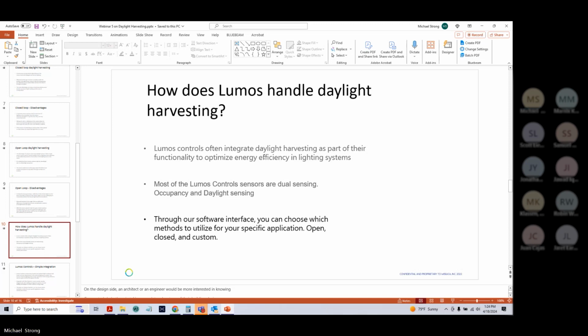All of our, or most of our sensors that we will recommend or specify are going to have dual sensing. And I mean dual sensing in terms of occupancy and daylight. You do not need a separate daylight sensor in order to have occupancy and daylight in an area. And through our software interface, you can choose which specific method you want to use. You can use open, closed, and or custom. You can make it a custom variation of the two.